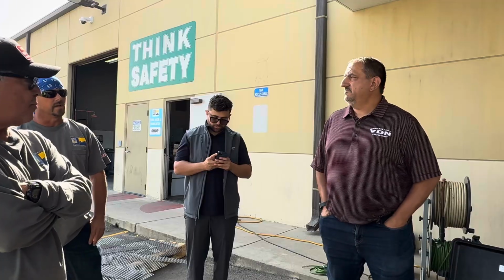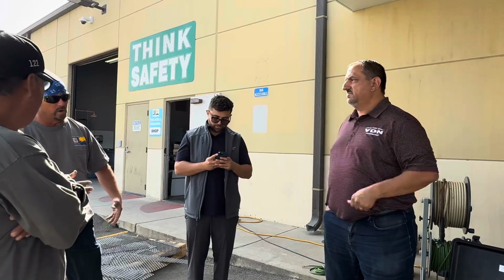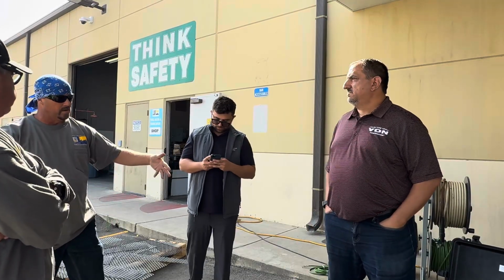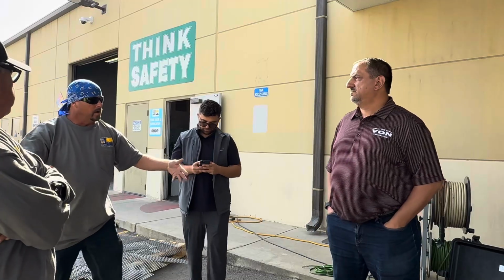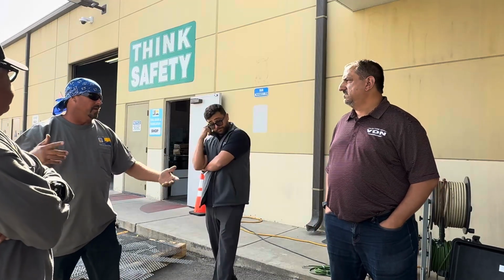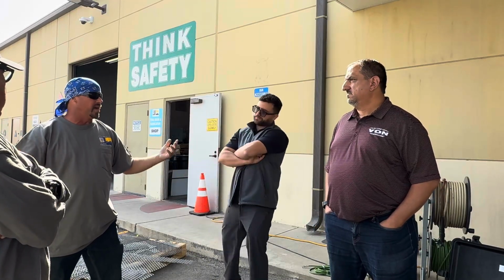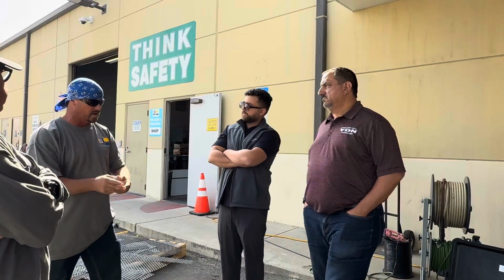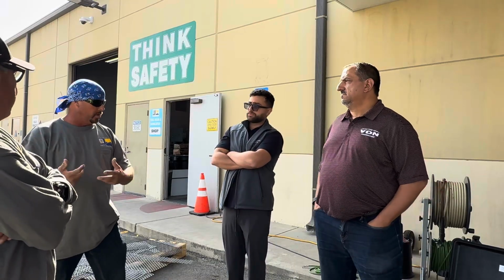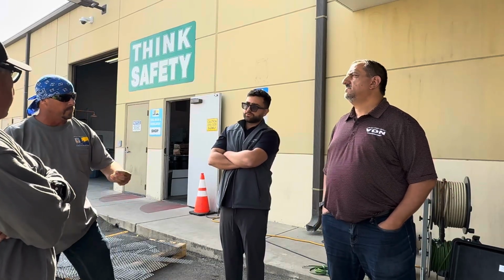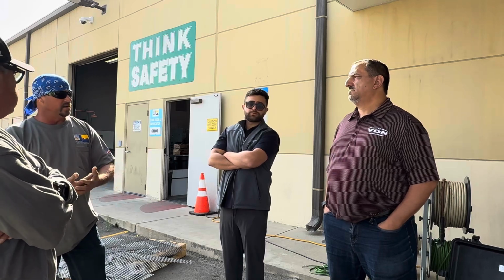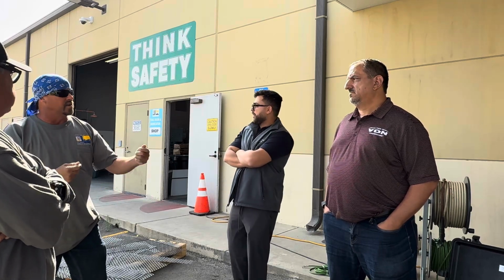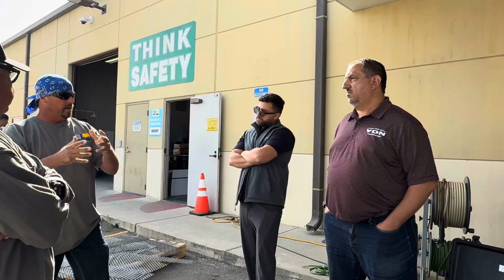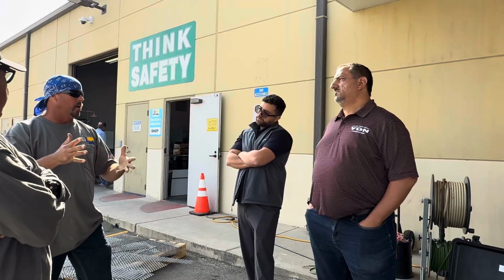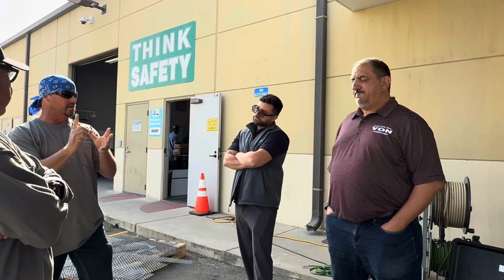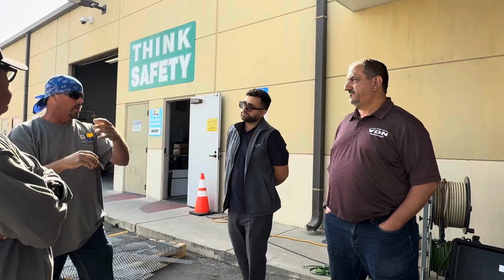So isolating the cable, like you said, we'll go out to a job where we're speculating there's a fault, and a lot of times in the middle of the night we may be able to back switch it. So guys will cut the cable or try to pull it out, and that's left like that. If you had a non-jacketed cable, you want to try to hook the concentric back into the system and peel everything back as if there's going to be an elbow on there, and try to isolate the conductor as if it was going to have an elbow on it.